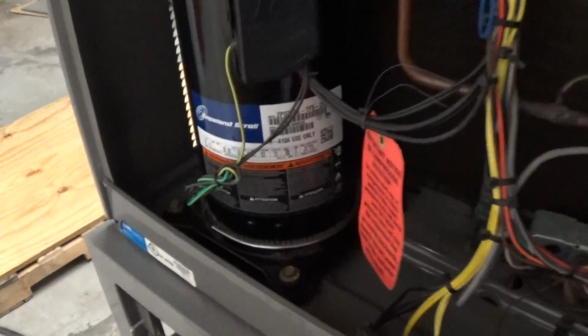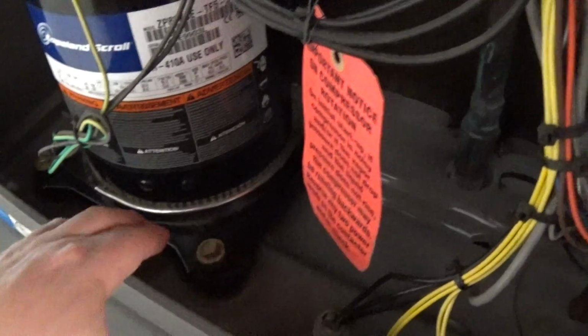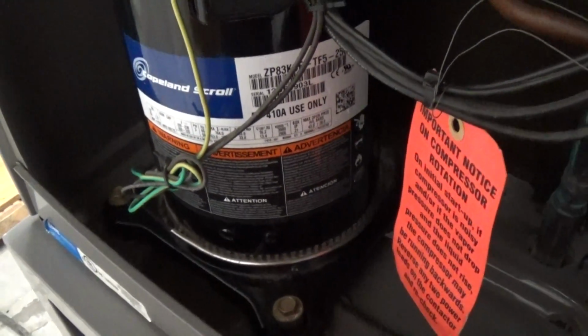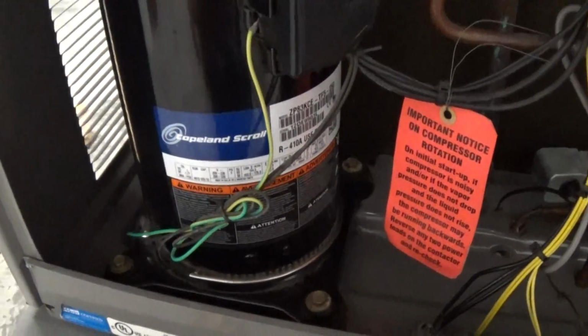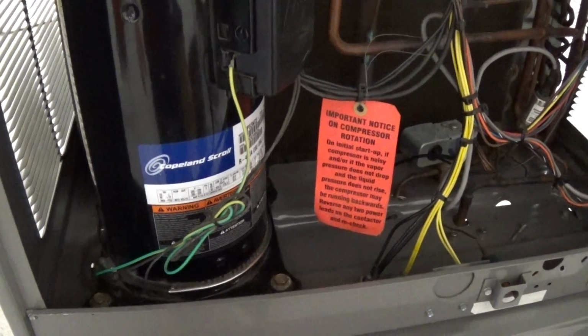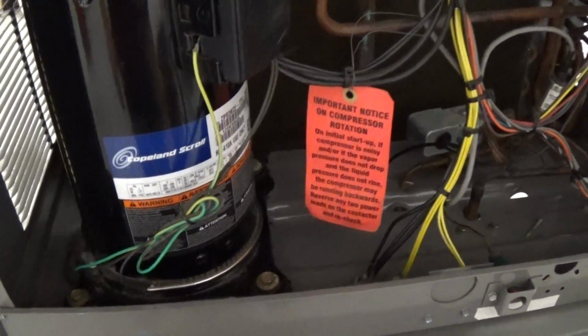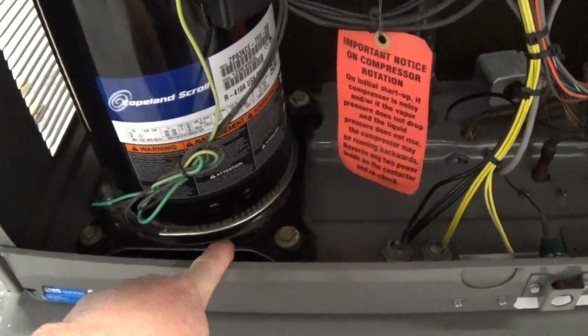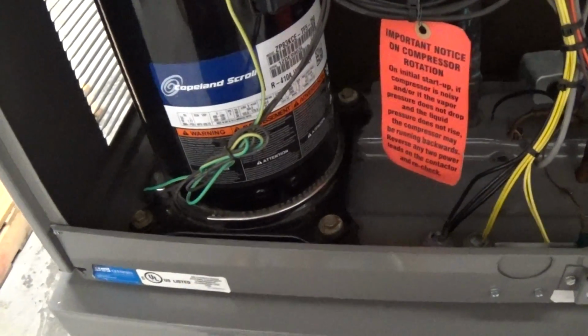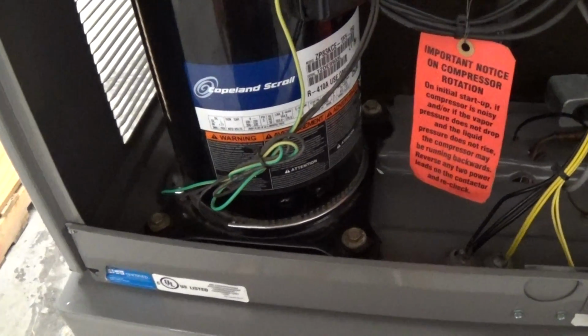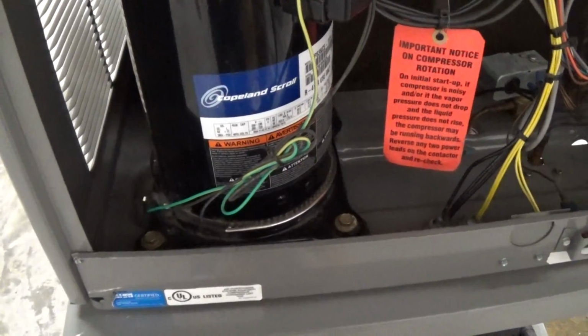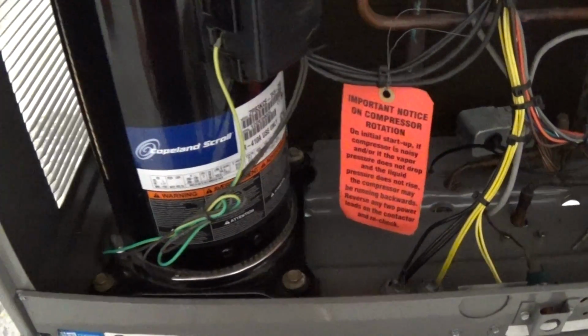This is an outdoor rated unit. This does have your crankcase heater for the compressor. It's always nice when you first do a startup to bring power to the unit, and as long as power is coming into the unit, the crankcase heater will stay warm.